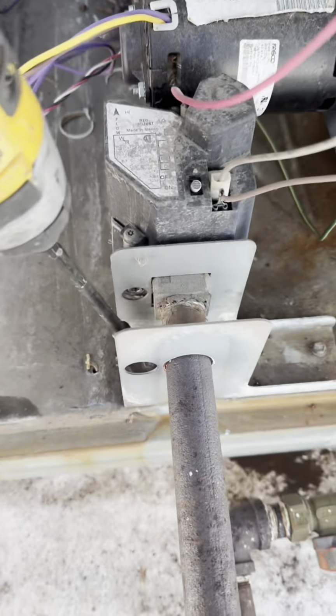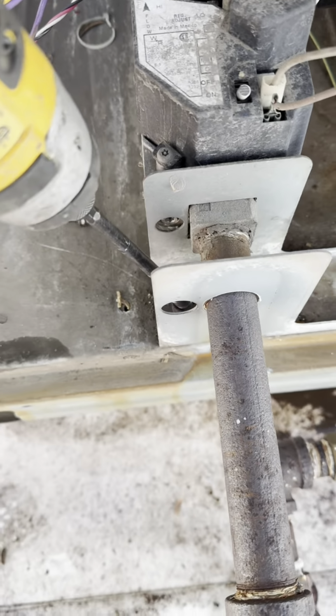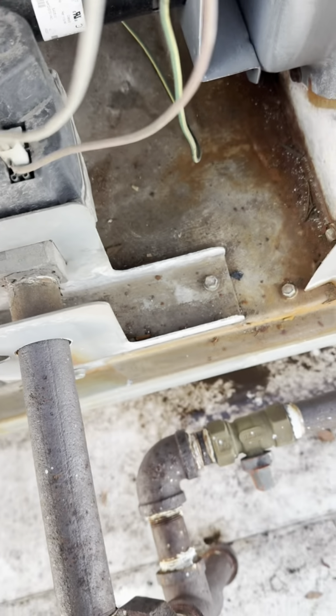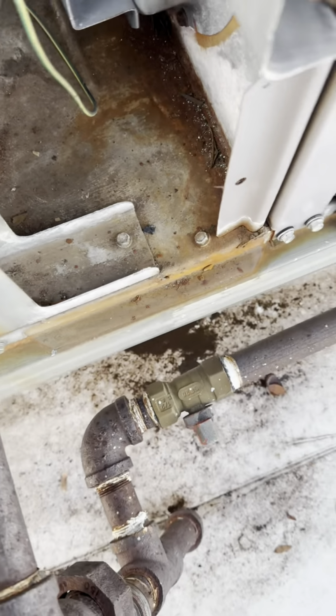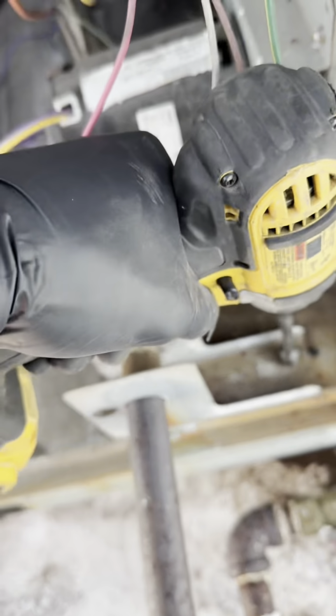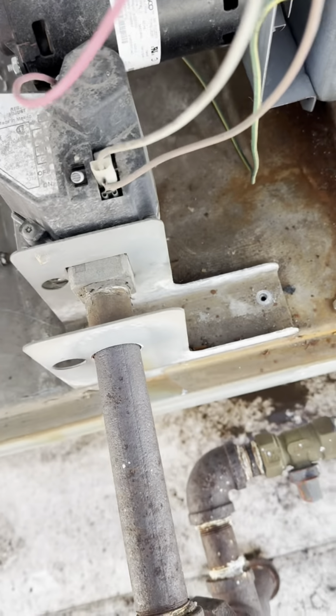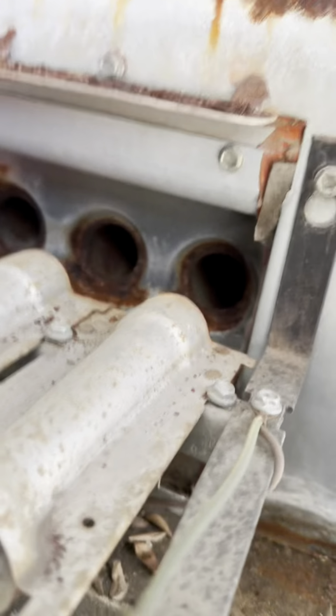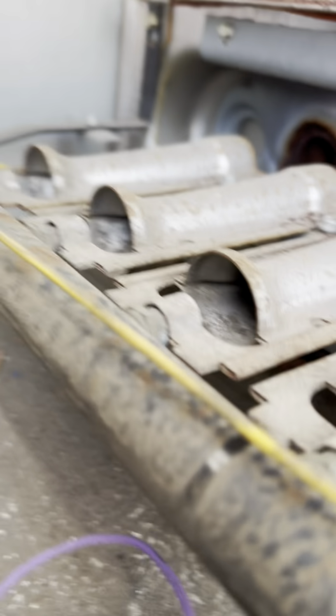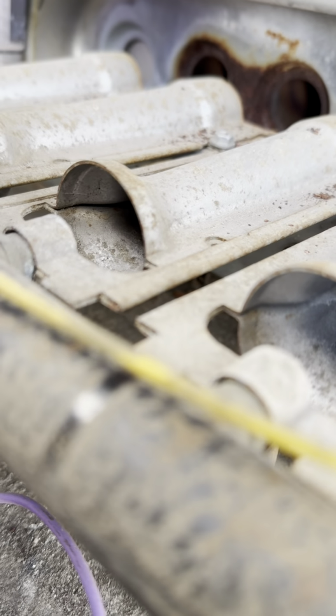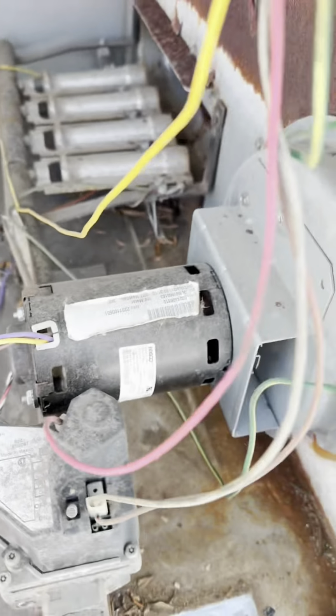So remove the gas valve support. Taking off some screws to get the burner out. Remove the burner screws. There's two of them, one on each side. And slide the burner out of the way.